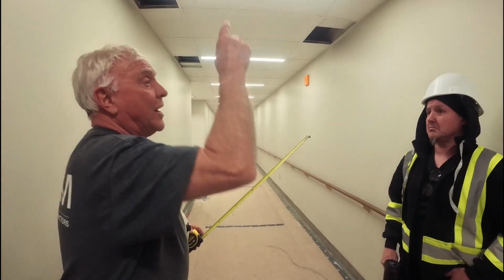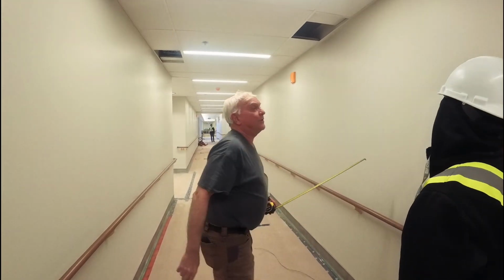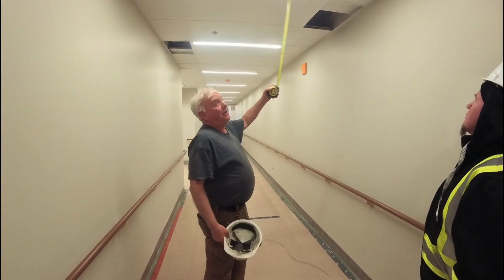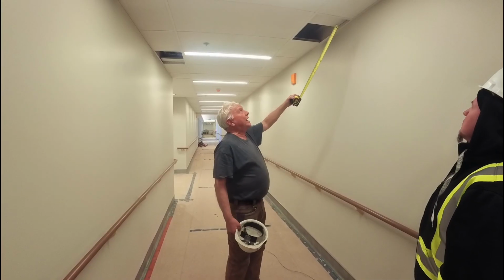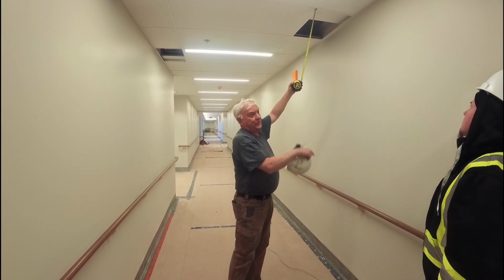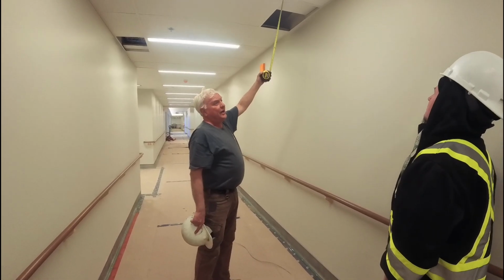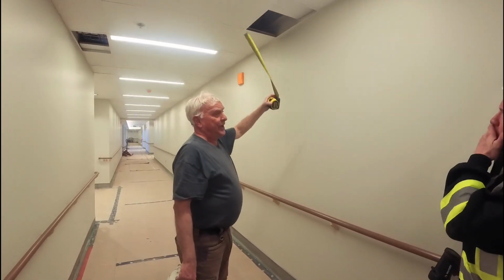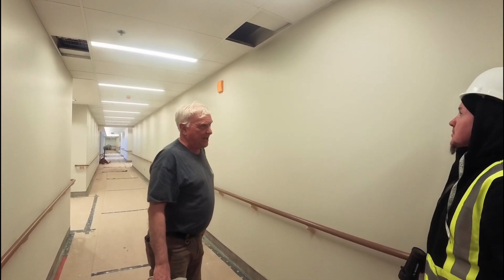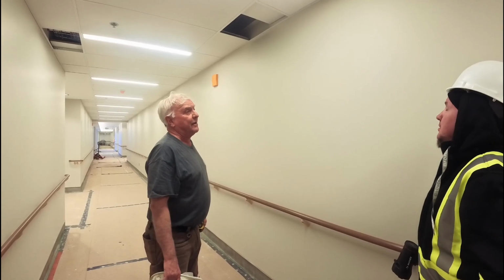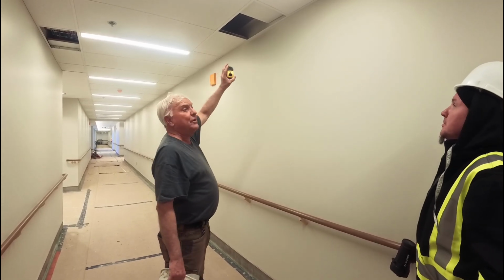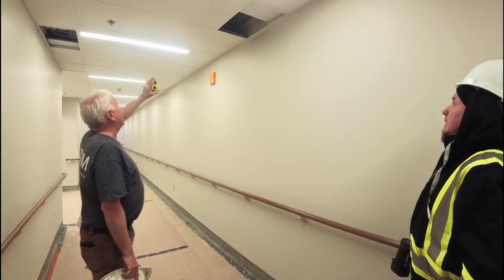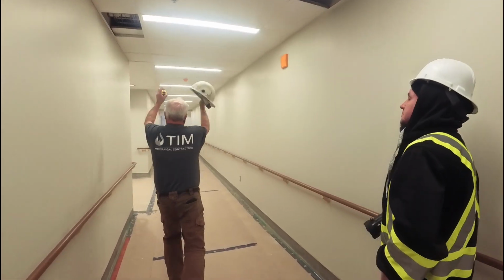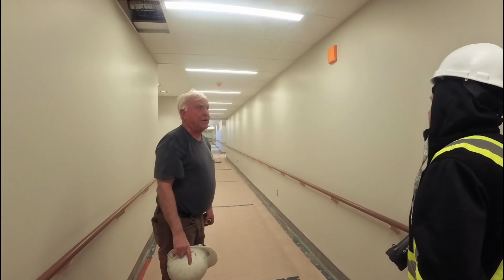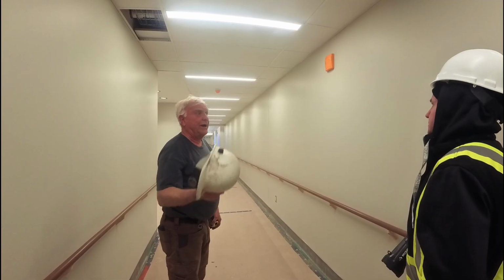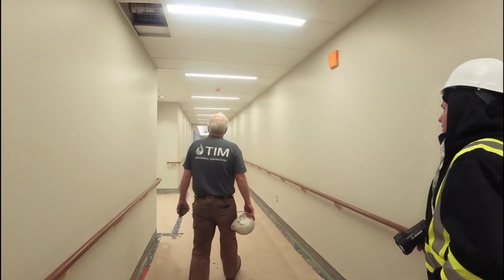But the return drop is actually in the laundry facility above us, and it comes through a large fire smoke damper in the wall. And I have my FSD sticker on the T-bar in the laundry facility, and I always put it on the side that has all the apparatus, the electrical tie-ins and the gauges and sensors and things that need to be looked at, right? This side, all it would have was just an angle frame around the fire damper sleeve. So again, it'll have a supply and return run going down the hallway, like any air handler does, one returning air to the air handler, one supplying air to the rooms, etc.